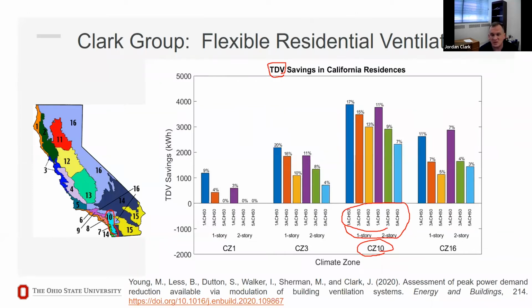But in the best ones, we can knock off something like 17%. This is annual TDV, so all of the real cost of electricity could be knocked off—17% of that total for the year—just by modulating ventilation during those peak times. So it's another way of adding that flexibility that's so needed for the new grid.